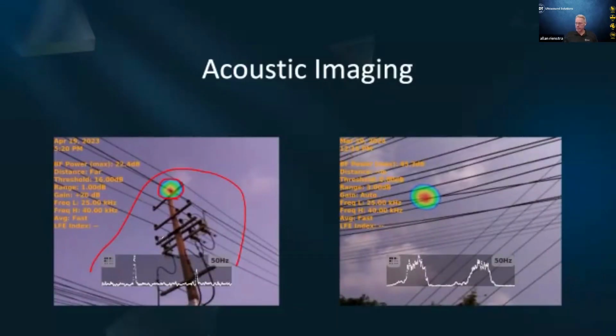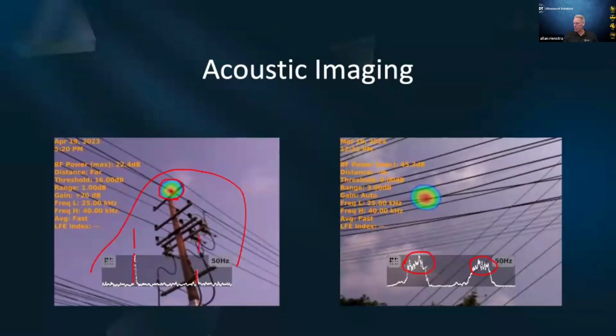Now, what that's telling us is that these other insulators are fine, but this insulator has some kind of breakdown issue. And we can look at the PRPD, or the phase resolved partial discharge illustration of that, and determine what type of failure it is. Here we know it's corona, because this is sort of extended out a little bit longer. And it's called phase resolved because we're looking at the 90-degree phase and the 270-degree phase of the entire signal. But when it's drawn out like this, it tells us it's more of a floating discharge than a specific discharge.